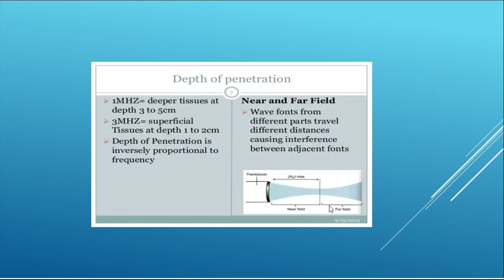Now let us talk about the near field and the far field. As we have discussed, in ultrasound, wave fronts from different parts travel different distances, causing interference between the adjacent fronts. You can see in the diagram, this is the near field and this is the far field. So some waves can cancel out or reinforce, so that the net result is a very irregular pattern of the sonic waves in the region close to the transducer face. This is called the Fresnel zone, also called the near field.